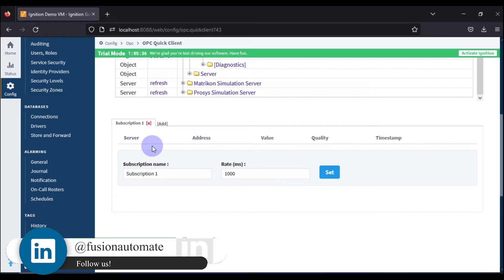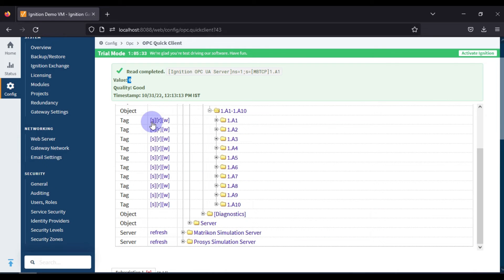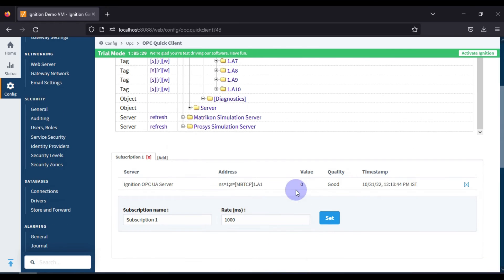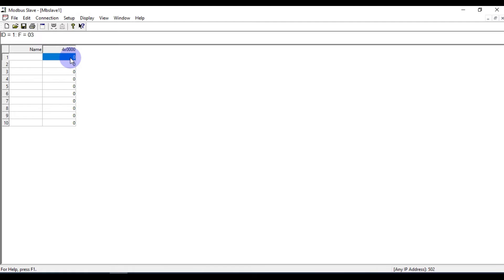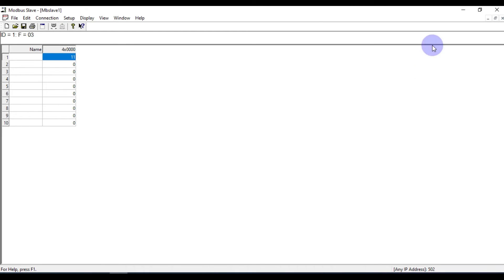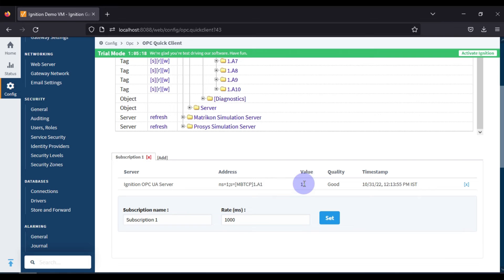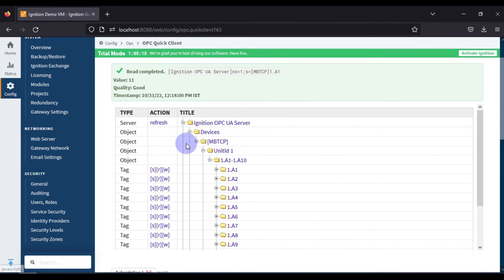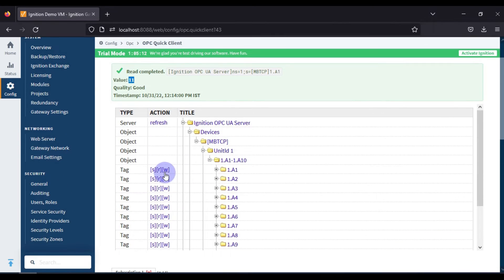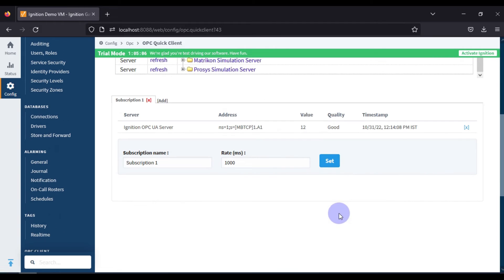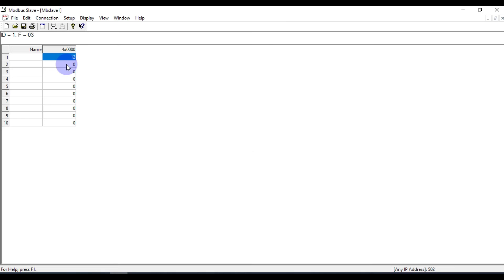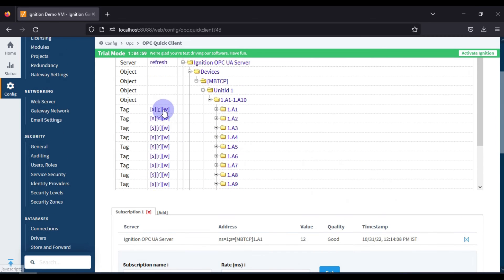If we subscribe to tag A1, the value shows as 0. Now if I go to my Modbus simulator and change the value to 11, you can see the subscribed value updates to 11. If I read from here it also shows 11. If I write the value 12 and press Write, you can see the value is now 12, both in the write result and the subscription. So this is Subscribe, Write, and Read — this is how you communicate your Modbus device with Ignition SCADA.